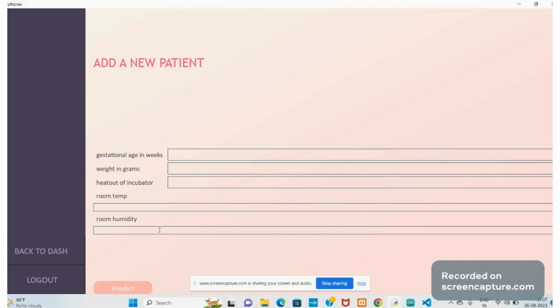They can choose to leave it. I added this because the room temperature and room humidity vary from place to place. We cannot fix it as constant for a particular city, because it depends upon the temperature of the room in which the incubator is placed. If the temperature is really high, estimating it based on the city's temperature and humidity can give faulty results. Or if that is totally fine for the user, they can always omit this.